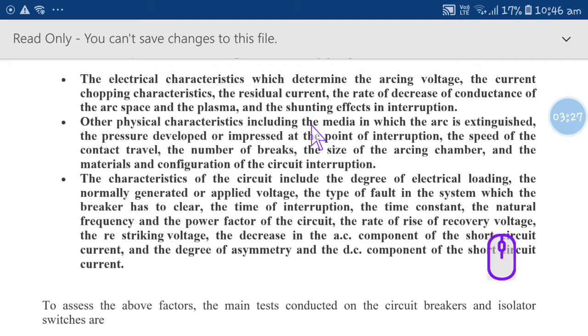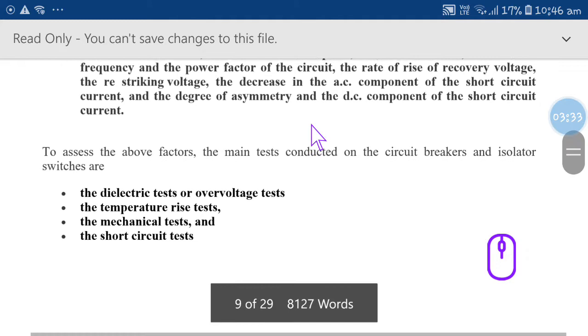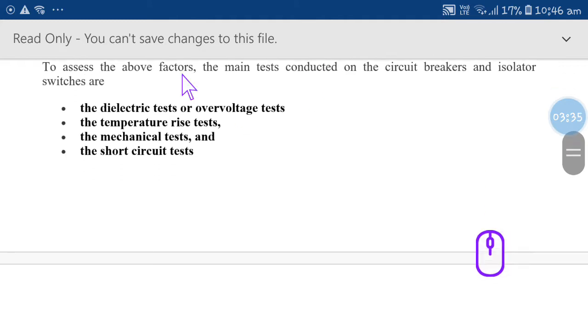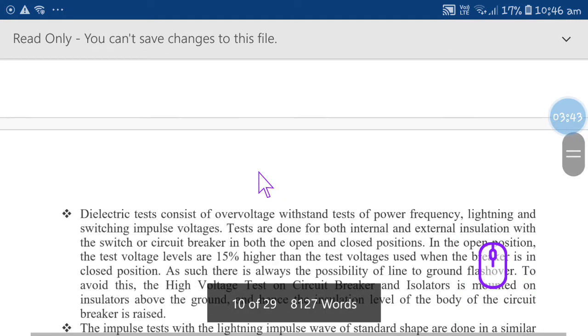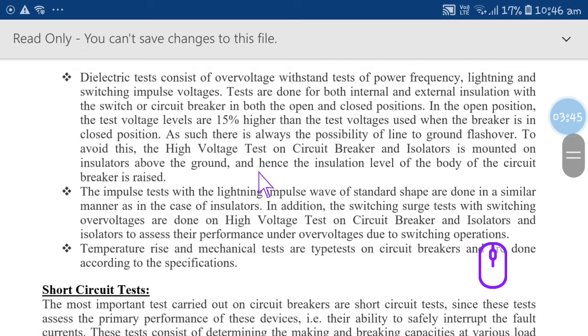They have given in depth what inductive current and capacitive current are and how exactly they take place. Now the main tests on circuit breakers and isolators are the dielectric test, temperature rise test, mechanical test and short circuit test. Let us go first with the dielectric test, before the short circuit test. The dielectric test consists of the voltage withstand test, the power frequency test, and lightning and switching impulse voltages.